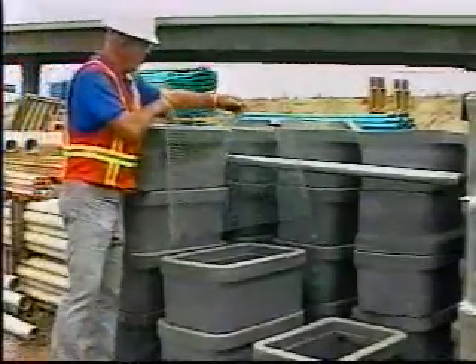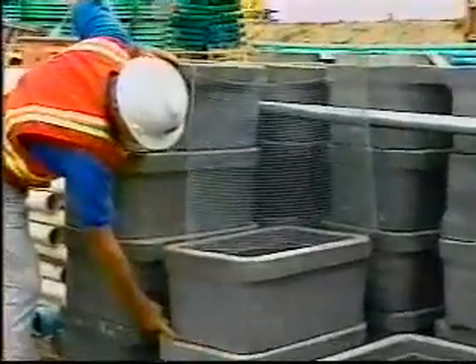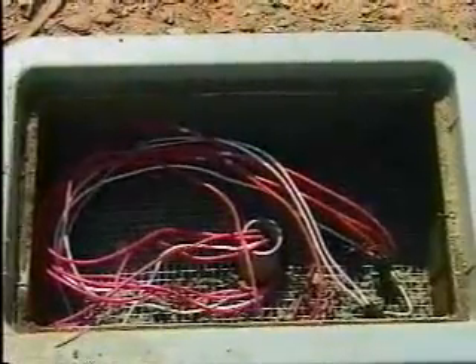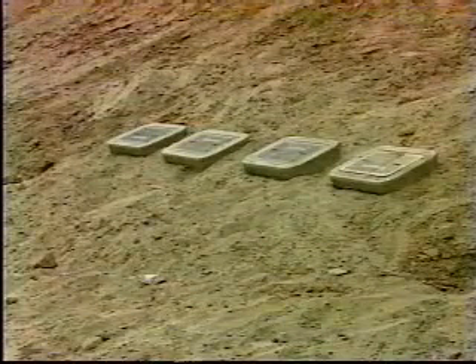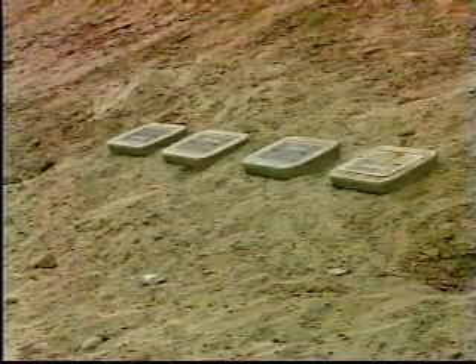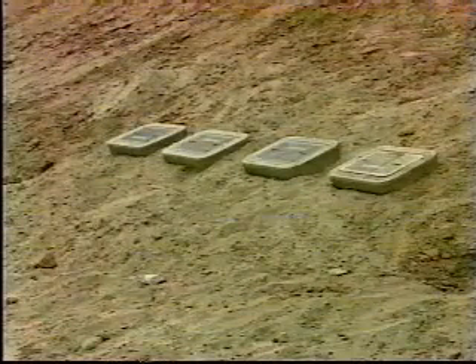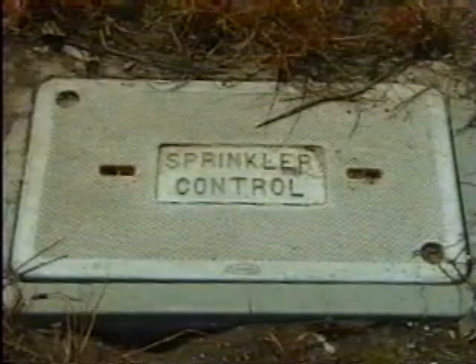Pull boxes are to be number five size or as shown on plans, set on half-inch mesh, 19-gauge, galvanized woven wire — commonly called hardware cloth — over six inches of one-half-inch to three-quarter-inch crushed rock. The hardware cloth is placed between the rock and the bottom of the pull box to prevent gophers from filling up the box with their diggings. In open ground, boxes are to be buried so their tops are two inches above surrounding grade. If the box is located in a paved area, the top is to be flush with finished grade.